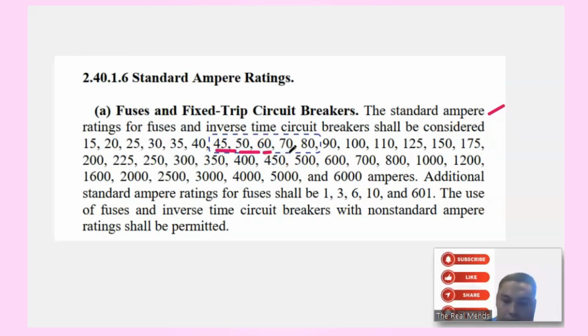So for me as a designer, if I use this 60 ampere circuit breaker, meron ka pang, if kunin mo yung 80% niya, 60 times 0.80, actually 48 amperes. So meron ka pang spare capacity kaysa sa 50 amperes medyo closest. So what if meron kang expansion sa future loads mo. So I use this 60 ampere trip circuit breaker.